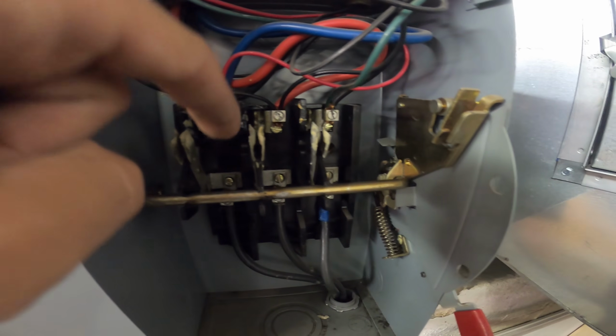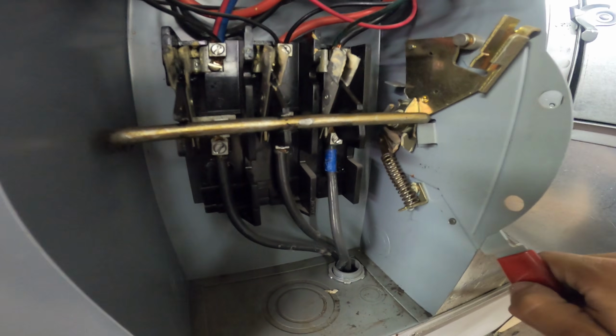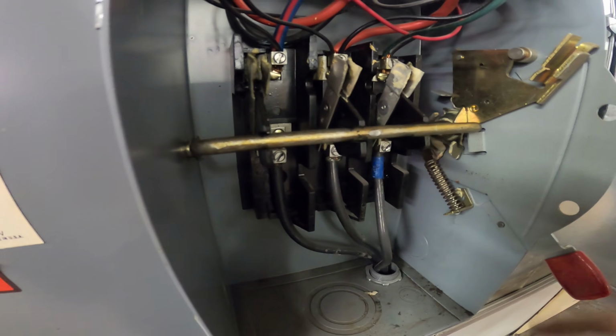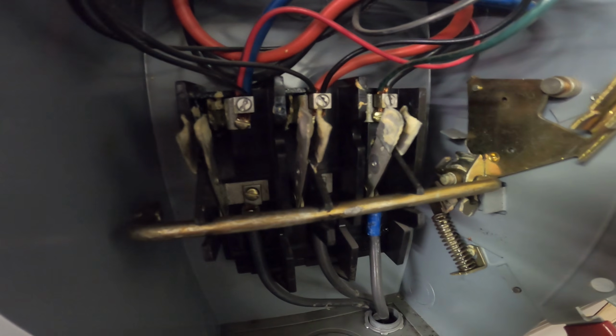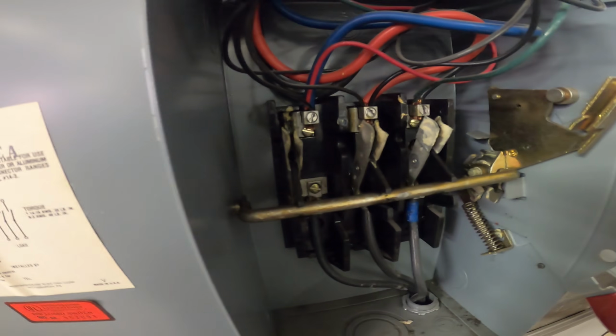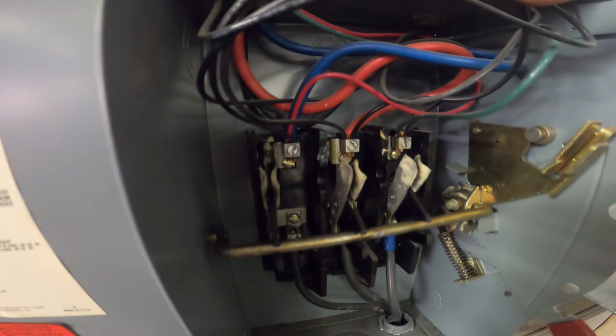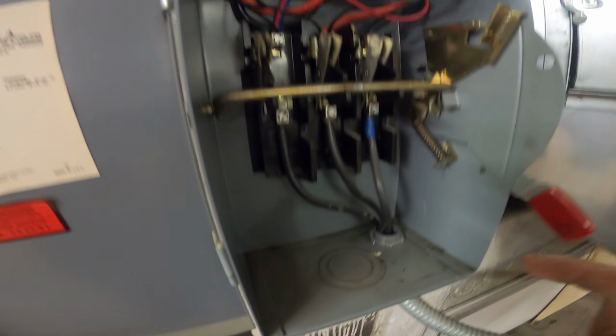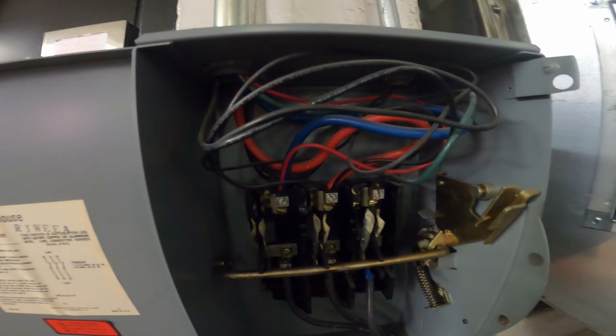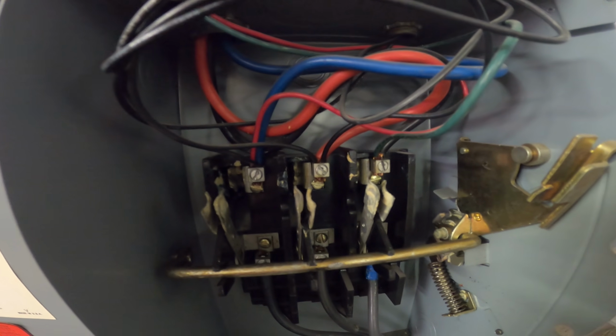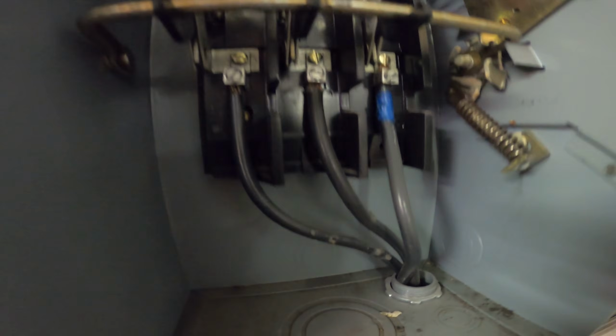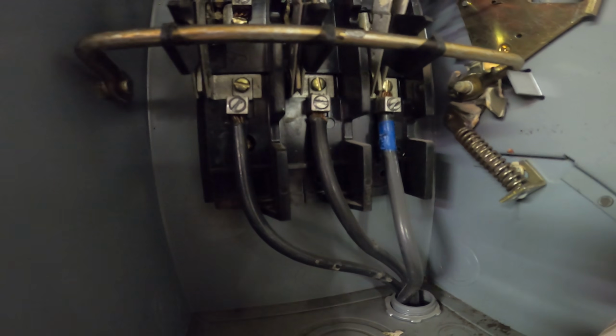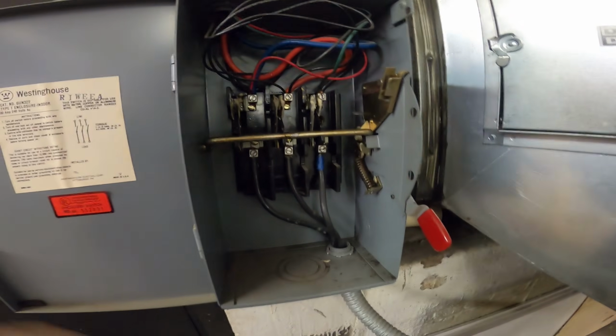If we look here on these little bars, once we move the lever, we actually adjust this bar and it gets in contact with the 3 wires and sends line voltage coming in from the top, because we can trace these wires and that feeds into the unit. So power comes in from the top. We've got 3 wires, 120 volts in each leg to ground, and that sends our 3-phase power here to our unit.